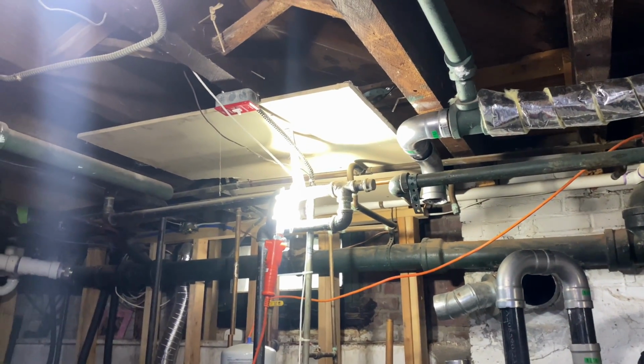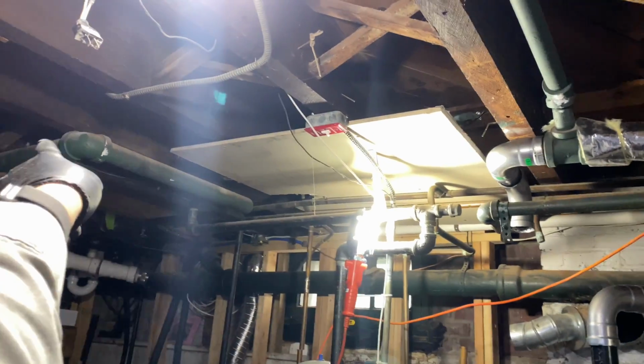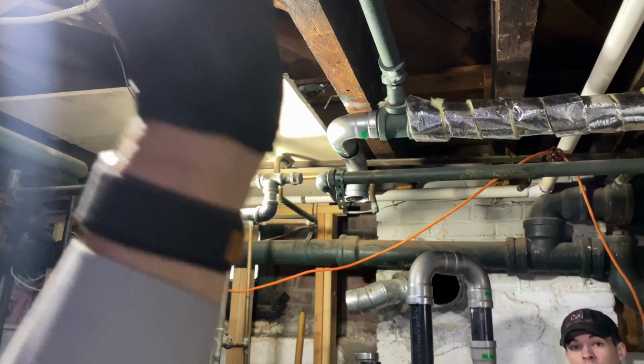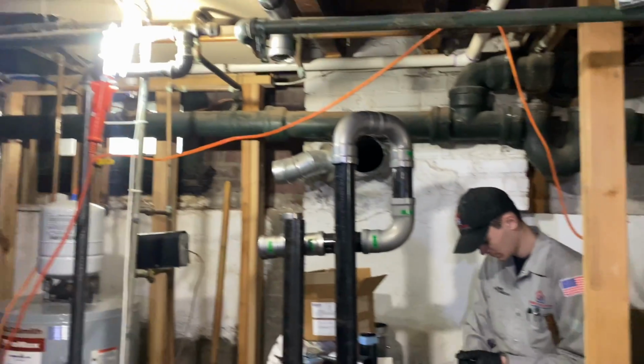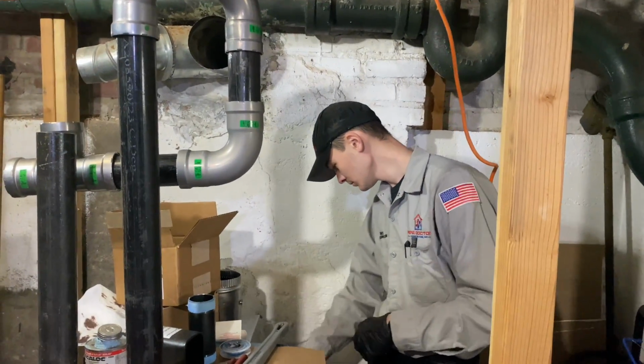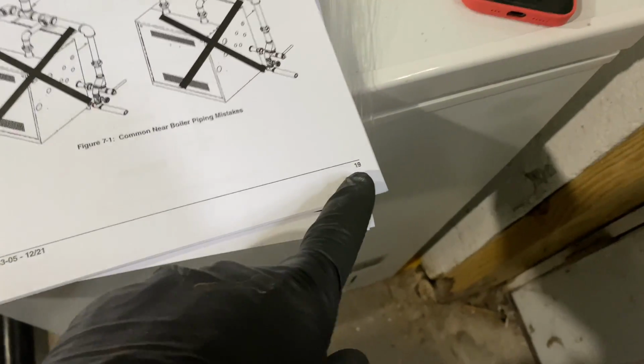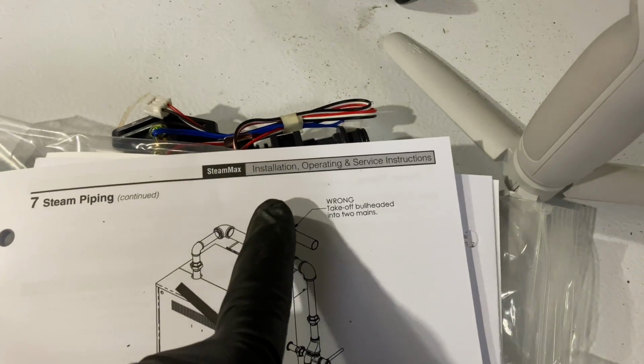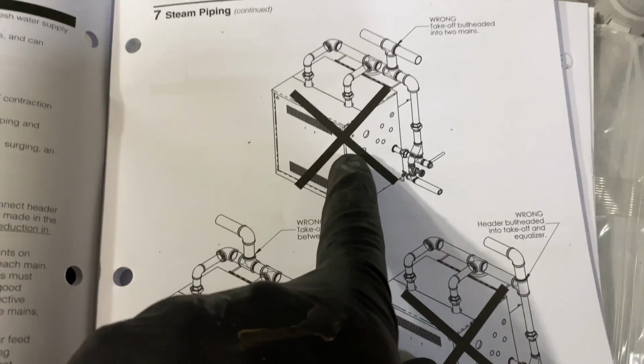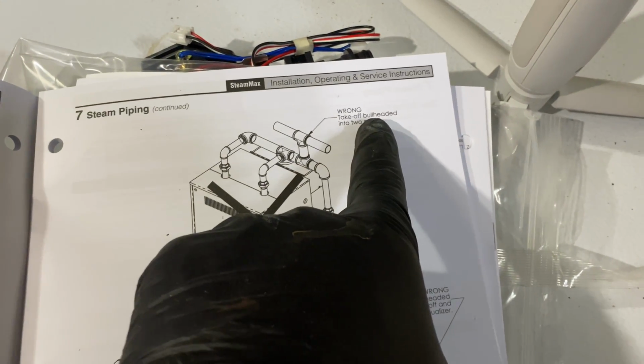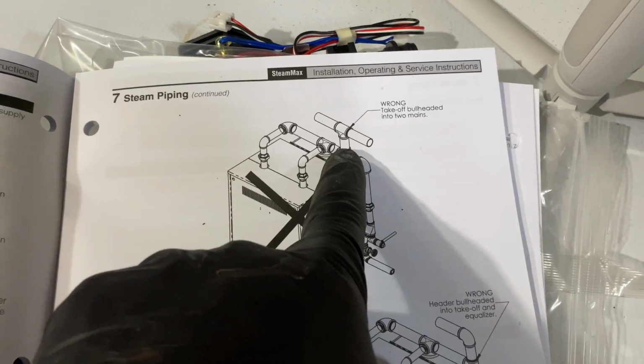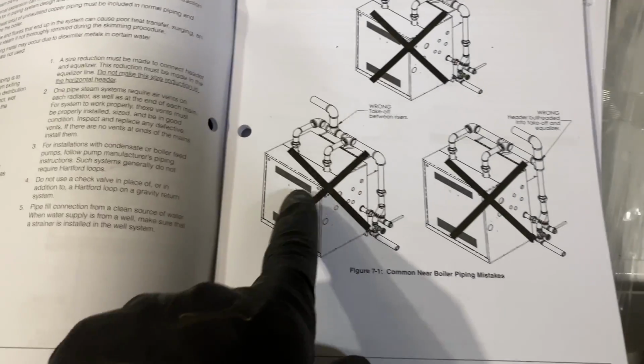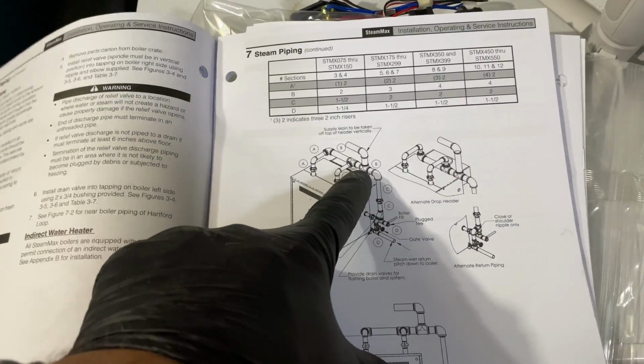If these were tied in together, we would never know. Exactly, if this was tied into there with a T in the middle, we would never know. However, when in doubt, defer to the manual. On page 19 of the SteamMax installation, operating, and service instructions, it says no, there's an X here, wrong, take off bullhead into two mains, you can't do that. That's what I wanted to do. That's a no good, even in the middle of those two, like this, no good either.